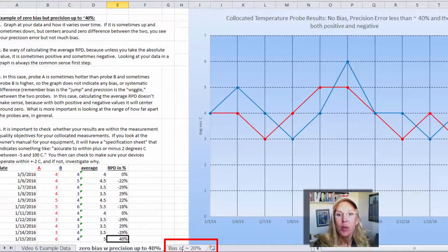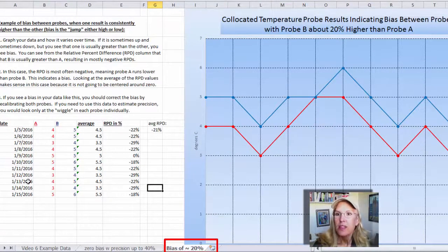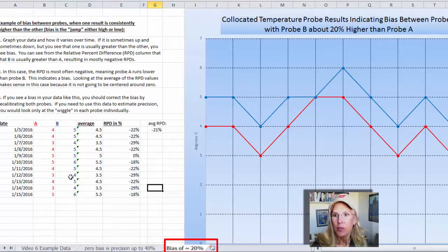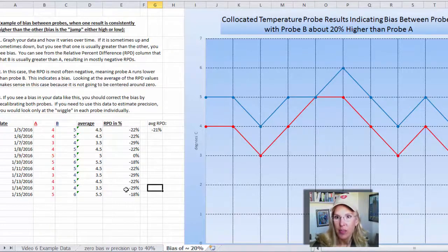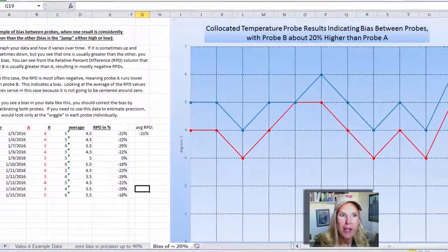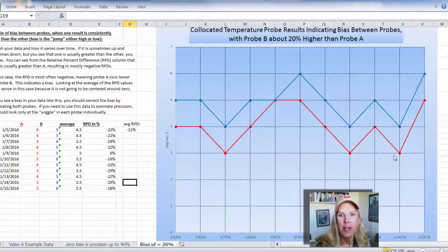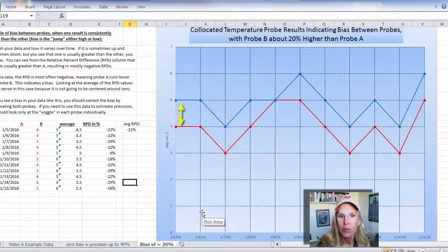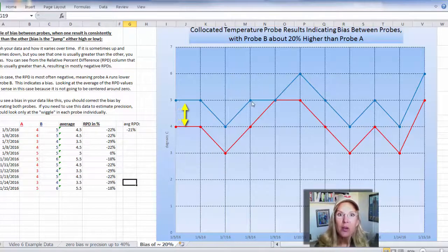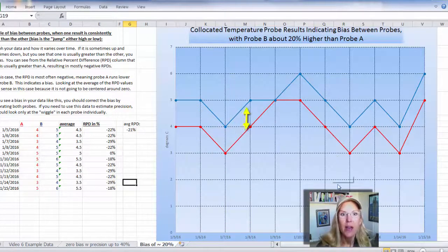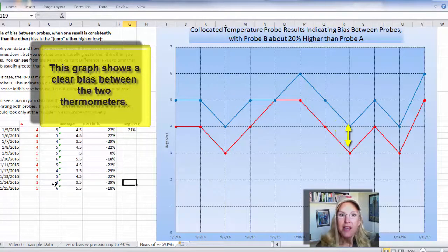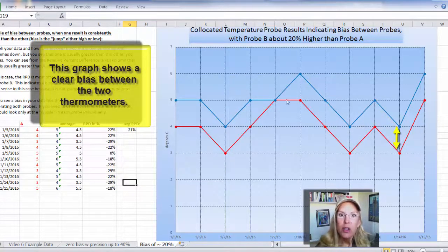The third sheet, labeled 'Bias of About 20 Percent,' shows similar data with date, the two temperature probe results in two columns, the average, and then the relative percent difference in percent. But if you look at the graph — and you always have to graph your data, it's so much easier to see what's going on with a graph than just looking down a row of numbers — you see a consistent difference between the two probes. You see, in fact, a bias. The blue line is consistently higher than the red line, meaning temperature probe B is always measuring the water to be a little bit hotter than temperature probe A.